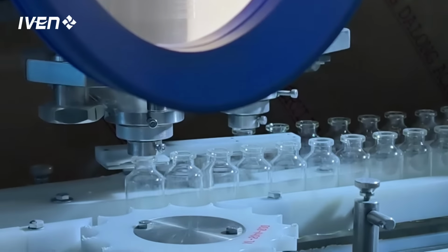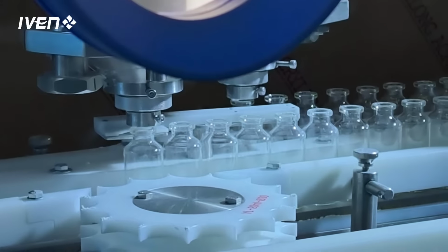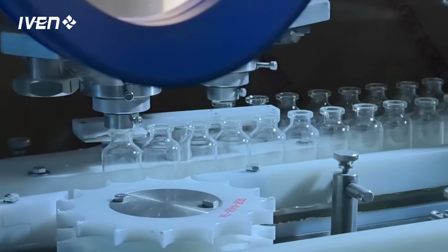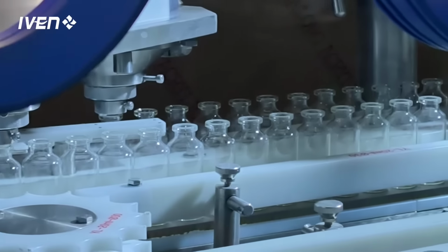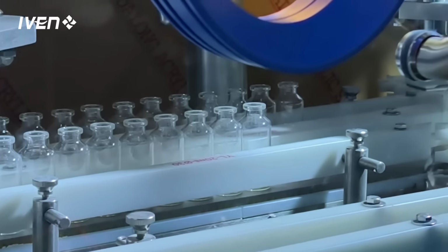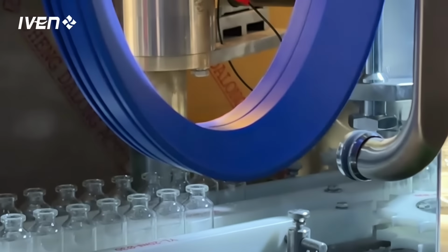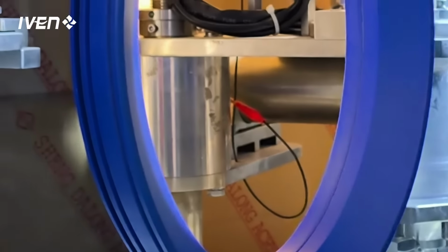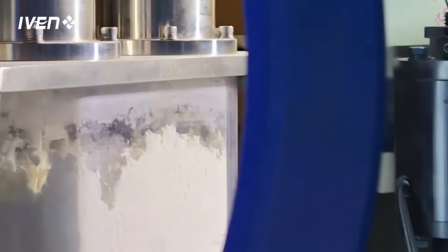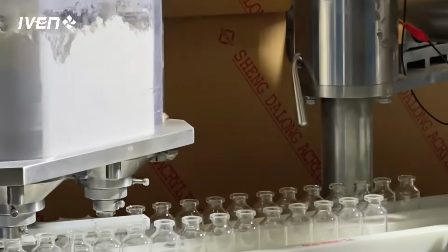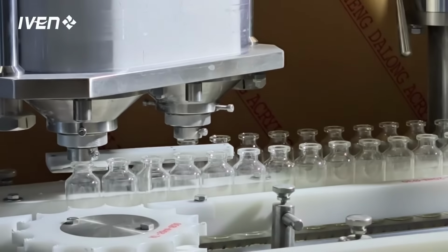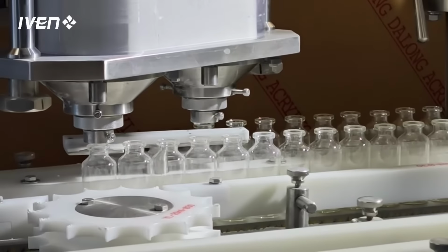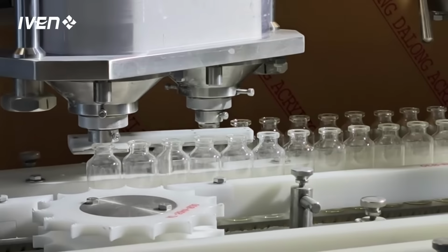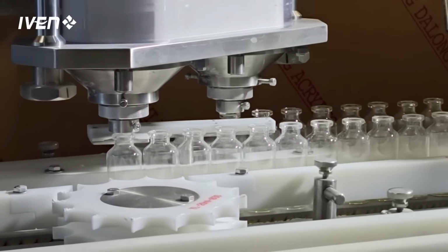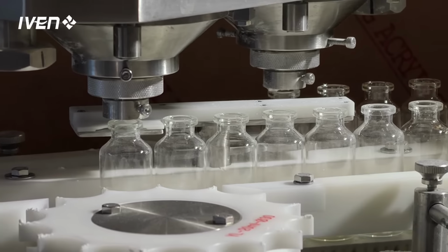The positioning of the vials can use cylindrical positioning or servo motor positioning, depending on the vial diameter. The advantage of servo motor positioning is accurate positioning, which enables automatic positioning and easy operation, with no need for operators to readjust. Cylinder positioning can reduce the customer's equipment maintenance cost and improve the speed of changing specifications. Customers can choose flexibly according to their own needs.